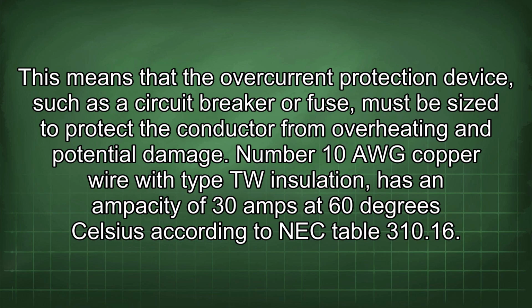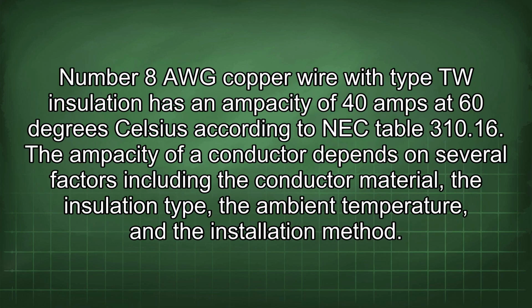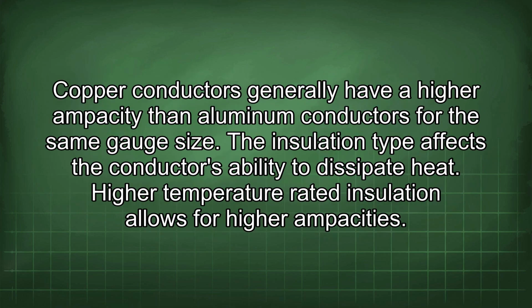Number 10 AWG copper wire with Type TW insulation has an ampacity of 30 amps at 60 degrees Celsius according to NEC Table 310.16. Number 8 AWG copper wire with Type TW insulation has an ampacity of 40 amps at 60 degrees Celsius according to NEC Table 310.16. The ampacity of a conductor depends on several factors including the conductor material, the insulation type, the ambient temperature, and the installation method. Copper conductors generally have a higher ampacity than aluminum conductors for the same gauge size. The insulation type affects the conductor's ability to dissipate heat. Higher temperature rated insulation allows for higher ampacities.